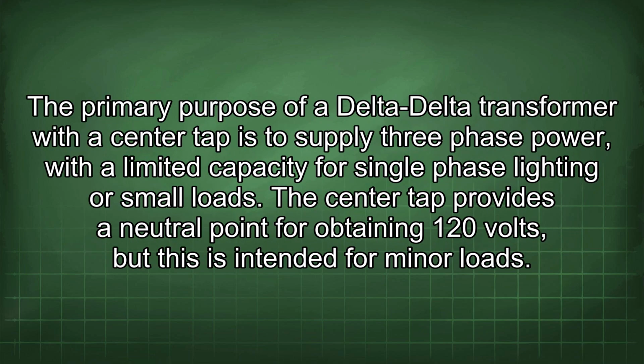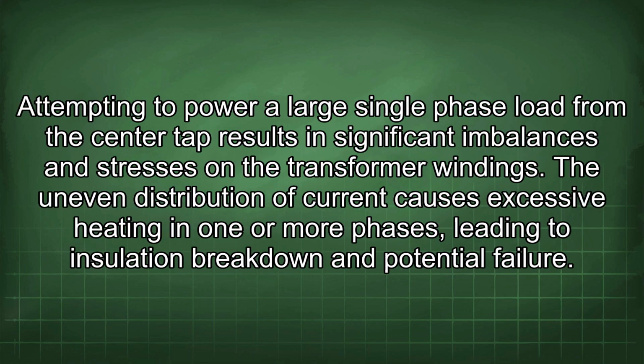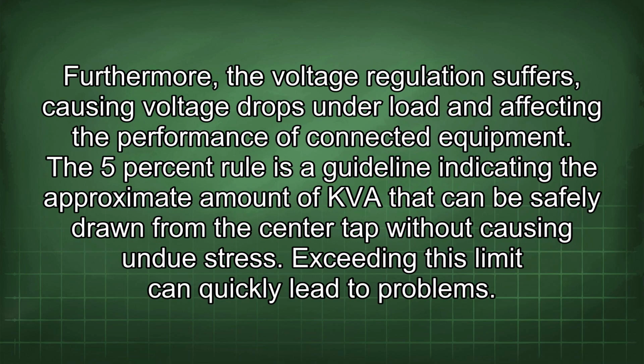The primary purpose of a delta-delta transformer with a center tap is to supply three-phase power with a limited capacity for single-phase lighting or small loads. The center tap provides a neutral point for obtaining 120 volts, but this is intended for minor loads. Attempting to power a large single-phase load from the center tap results in significant imbalances and stresses in the transformer windings. The uneven distribution of current causes excessive heating in one or more phases, leading to insulation breakdown and potential failure. Furthermore, the voltage regulation suffers, causing voltage drops under load and affecting the performance of connected equipment.